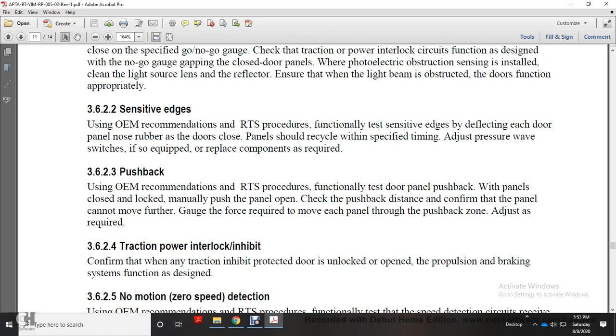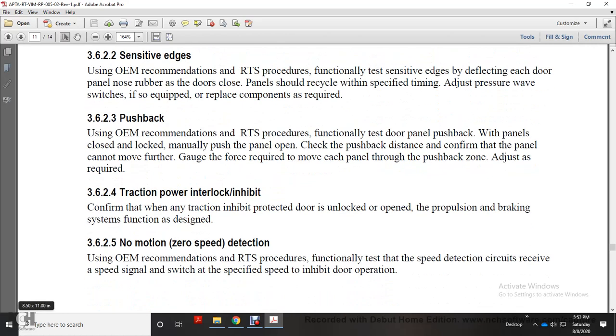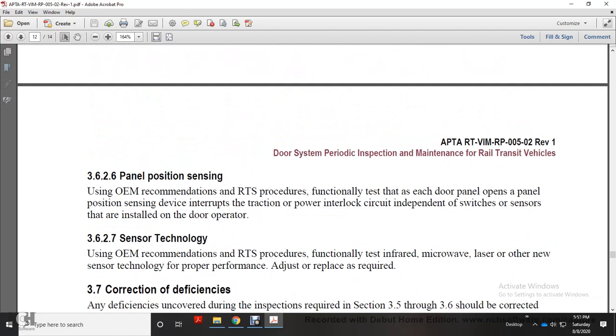3624, traction power interlock. Confirm that traction is inhibited when the door is unlocked or open, and that the propulsion and braking system function as designed. 3625, no motion, zero speed detection. Using the original equipment manufacturer recommendation and rail transit system procedure, functionally test the speed detection circuit, which receives the speed signal and switches at the specified speed to inhibit door operation.